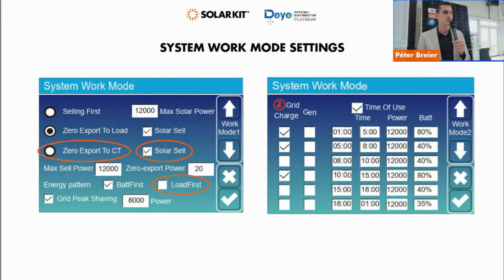Solar Sell is basically the 0 inject settings. So if solar cell is marked, then the inverter will be able to feed back onto, or inject back into the grid. If the mark is removed, the inverter will not inject back anything into the grid. This is separate for 0 export to load, and this is separate for 0 export to CT. So make sure that you put the mark in the same row which mode you are using.